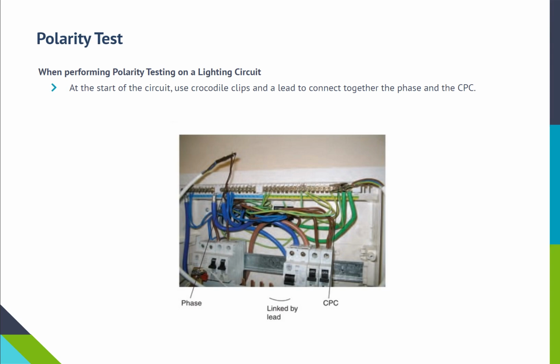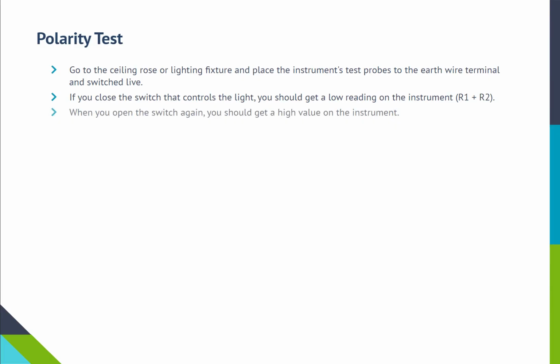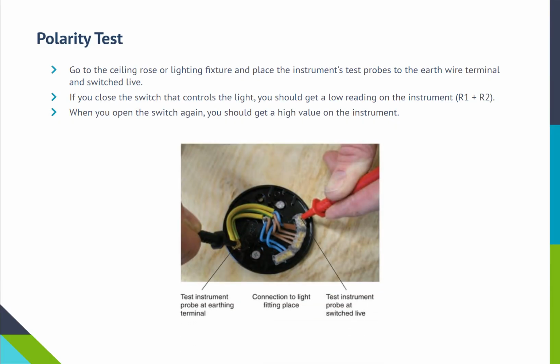When performing polarity testing on a lighting circuit, at the start of the circuit, use crocodile clips and a lead to connect together the phase and the CPC. Go to the ceiling rose or lighting fixture and place the instrument's test probes to the earth wire terminal and switched live. If you close the switch that controls the light, you should get a low reading on the instrument, R1 plus R2. When you open the switch again, you should get a high value on the instrument.